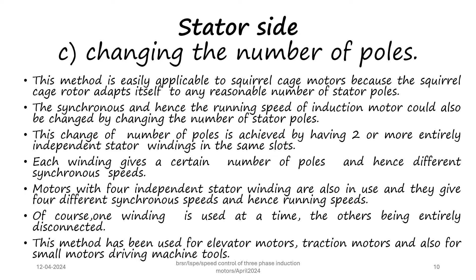The third method of speed control from the stator side is by changing the number of poles. This method is easily applicable to squirrel cage motors because the squirrel cage rotor adapts itself to any reasonable number of stator poles. The synchronous and hence the running speed can be changed by changing the number of stator poles. This is achieved by having two or more entirely independent stator windings in the same slots — each winding gives a different number of poles and hence different synchronous speeds. Motors with four different independent stator windings give four different synchronous speeds; one winding is used at a time. This method is used for elevator motors, traction motors, and small motors driving machine tools.